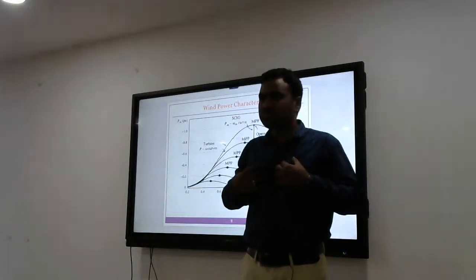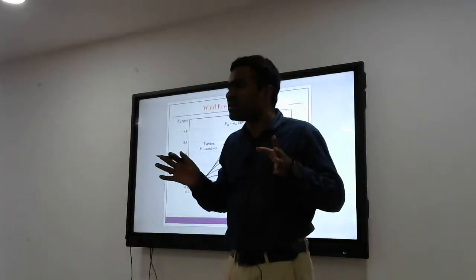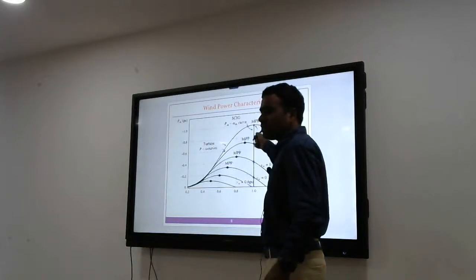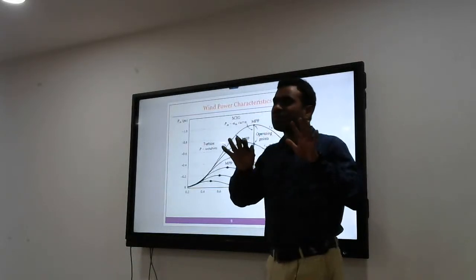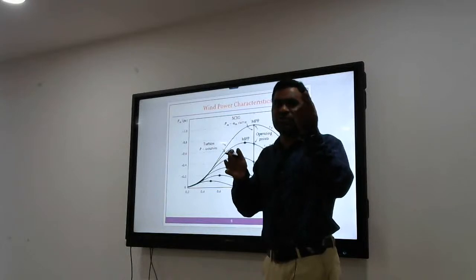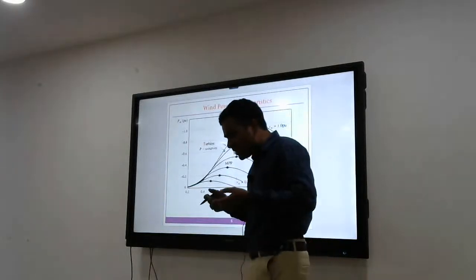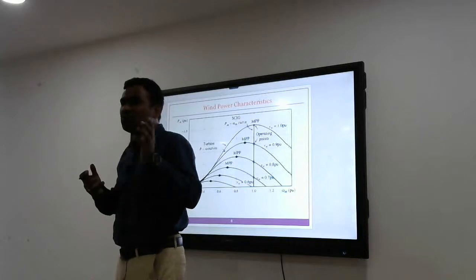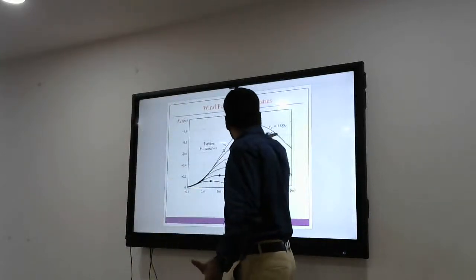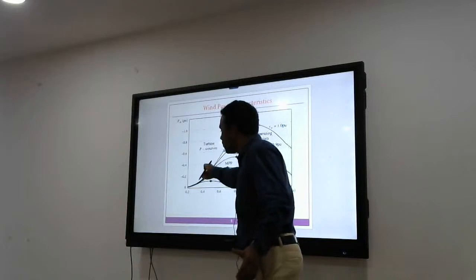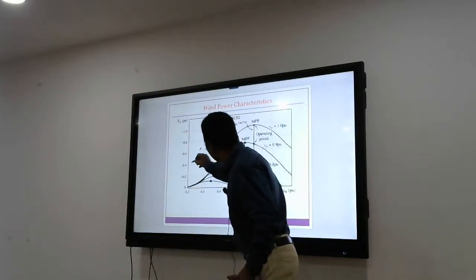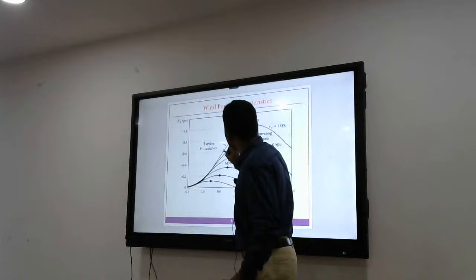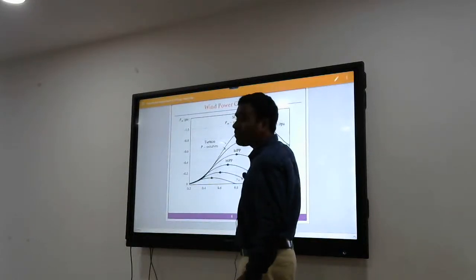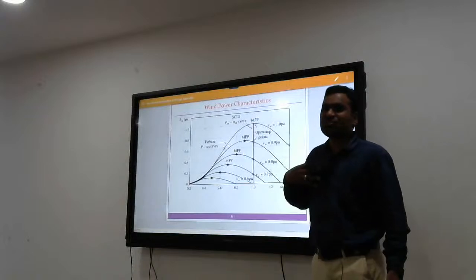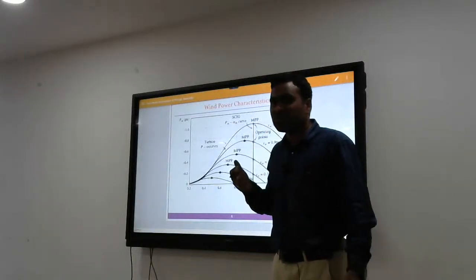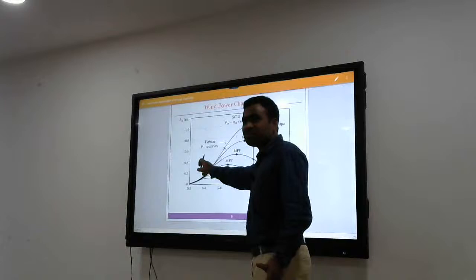Even if I assume my wind speed is constant, that is 1 per unit, it doesn't mean the power is constant. If I have a particular wind speed, 12 meters per second, even then your power is not constant. If this is 1.0 per unit, this is the curve you will get. You may get power of 0.4, you may get power of 0.6, you may get power of 0.8, you may get power of 1 per unit, even though my wind speed is constant.